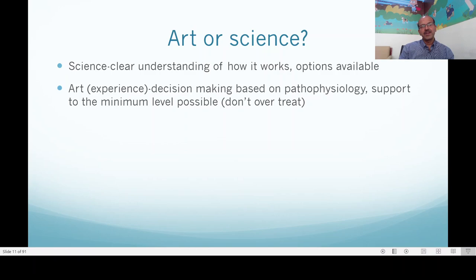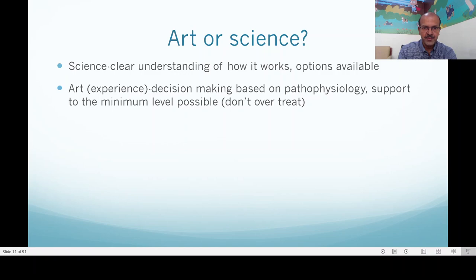We need to think about whether ventilation is a science or an art — and the answer is that it is a combination of both. The science involves understanding the ventilator, the circuit, the machine, how it works, the microprocessor components, and what we can do to improve. We now have continuous oxygen monitoring and feedback-based adjustment of FiO2 in most ventilators. The same ventilator can now deliver most modes — from high flow nasal cannula, NIPPV, CPAP, invasive ventilation, NAVA, and even high frequency ventilation. Flow sensors are becoming more responsive and processor times have reduced.